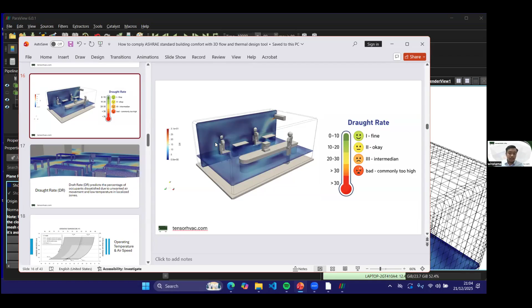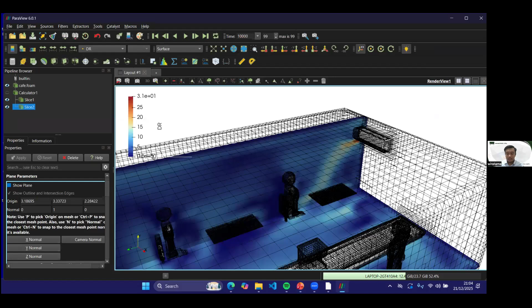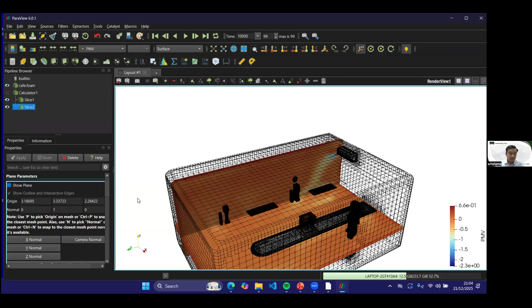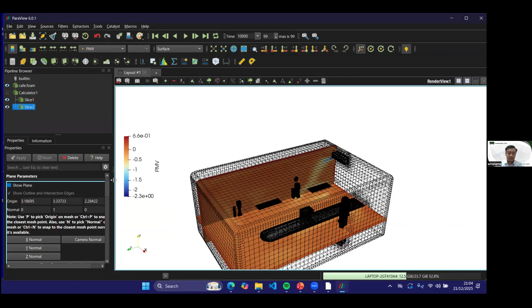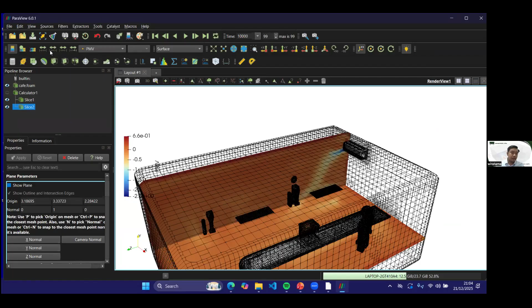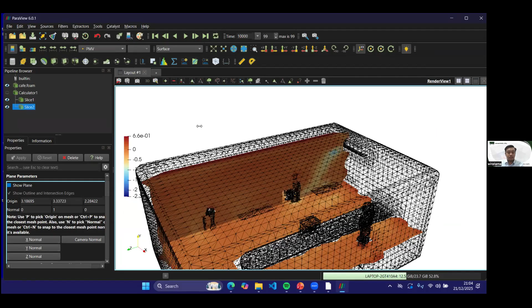Okay, let's check another parameter, which is PMV. Here we see the distribution is from minus 2.3 to 0.66, which is beyond ASHRAE 55, but don't worry, it's just automatically generated. So let's change our range to ASHRAE standards, which is minus 0.5 to 0.5.